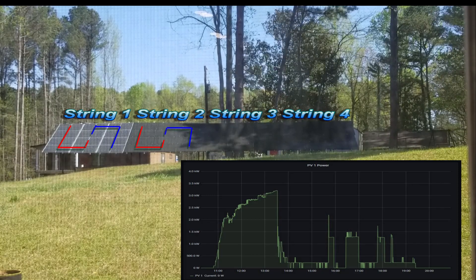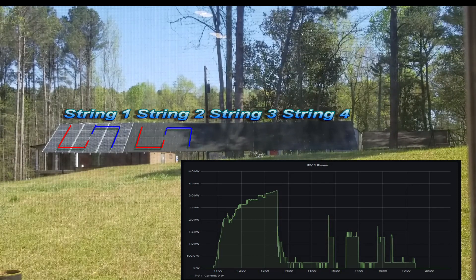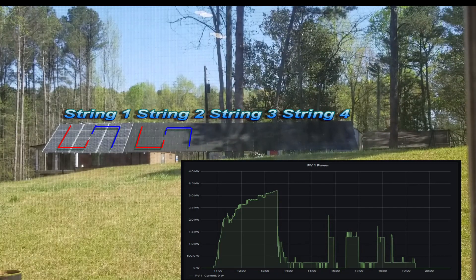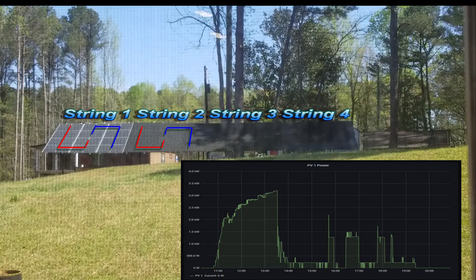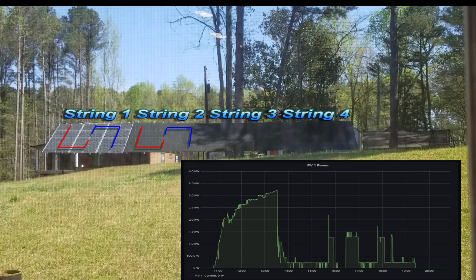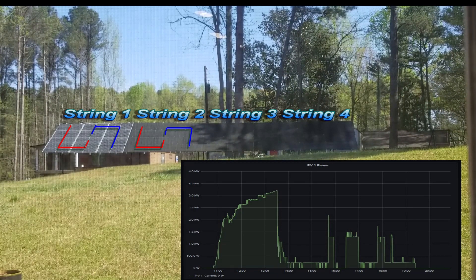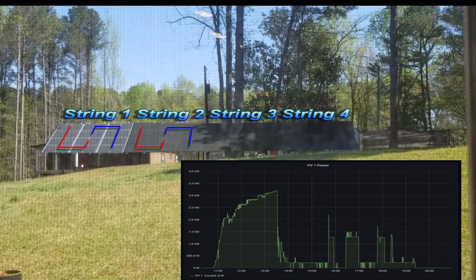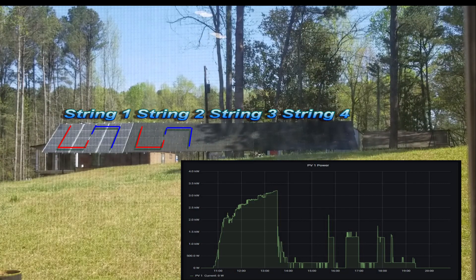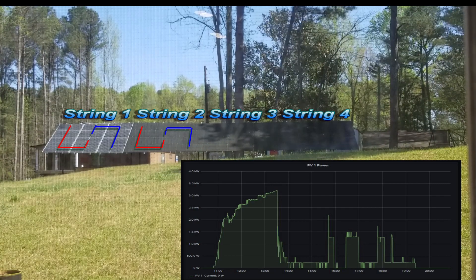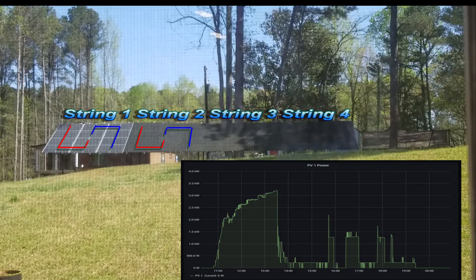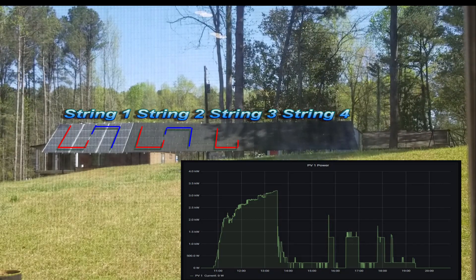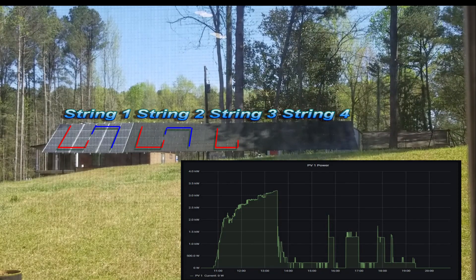On the bottom graph you can see data pulled straight out of inverter 1, and it shows the production during the sun hours. For April it's from 11 to 7 on a bright sunny day. It will be interesting to see how this looks during the entire summer with the cloudy times, but for now this works best for me.